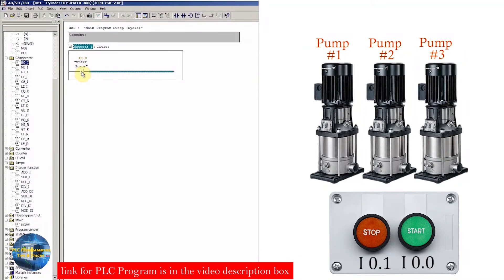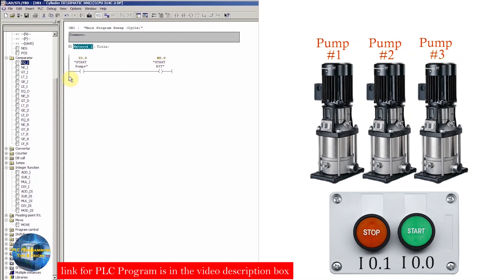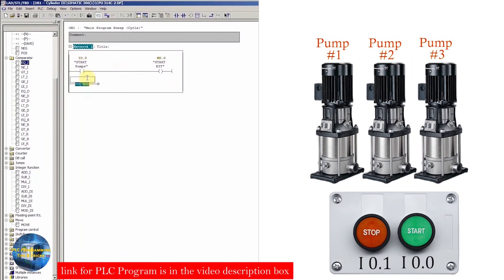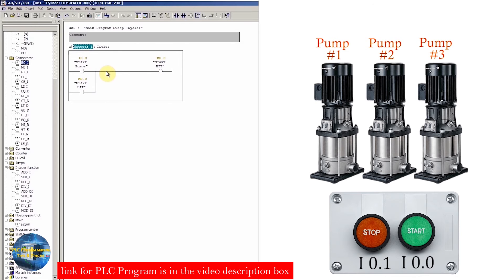Whenever we press the start push button, we have to hold on memory bit M0.0, which is the start bit. To hold on, we will insert a branch with a NO contact and assign it the same M0.0 to latch through its own contact. To turn off this start bit, we will insert a NC contact assigned to I0.1, which is our stop push button.